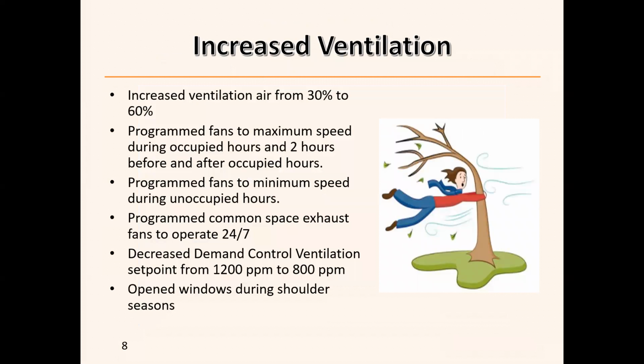The first thing we did was to increase the ventilation air from 30% to 60%. This is more than the industry standard requires for fully occupied spaces, and our spaces were never planned on being fully occupied. As a side note, the industry standard we are referring to is the ASHRAE Ventilation Standard 62.1.